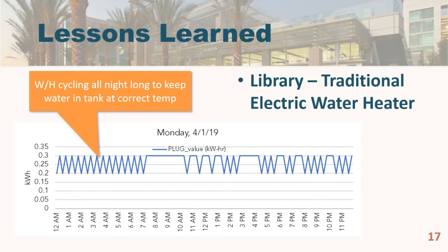This is a library, so there's not a whole lot of need for hot water. One lesson we've learned is that in a building like this, where there isn't much need for hot water, it's recommended to use Insta-Hots or point-source water heaters instead. Even though that looks like a very small amount of energy use, it can add up over time — and in a zero net energy building, we don't want any excess energy if we can help it.